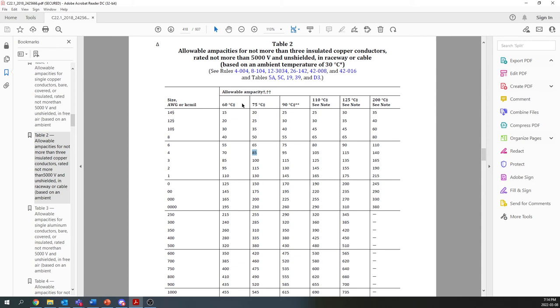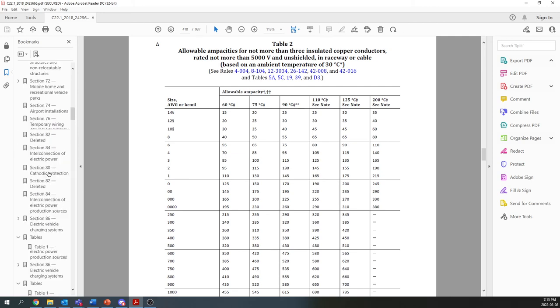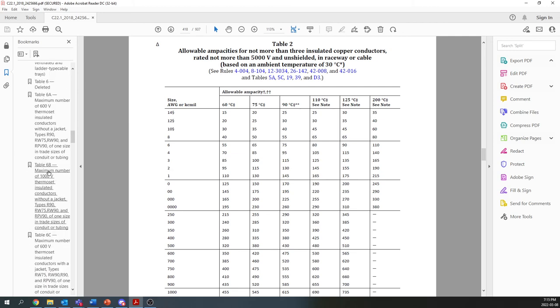So after applying those two correction factors, we are now going to be installing three number 2 wires and two number 4 wires, plus our ground wire, which is number 2. This shows you the iterative design that we have to go through to pick our wire sizes. The ground wire is always matched to the biggest conductor in your system. Even though we're pulling two circuits, we don't have to pull two ground wires. We just have to pull one, as long as it's matched to the biggest wire that you're pulling into your cable.